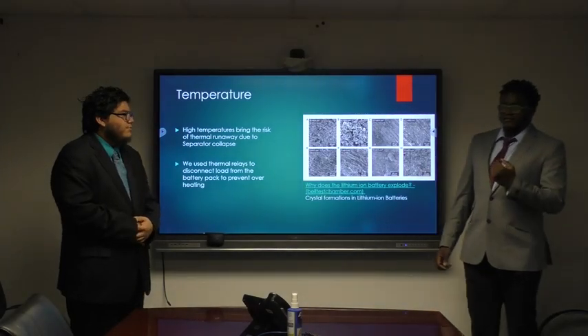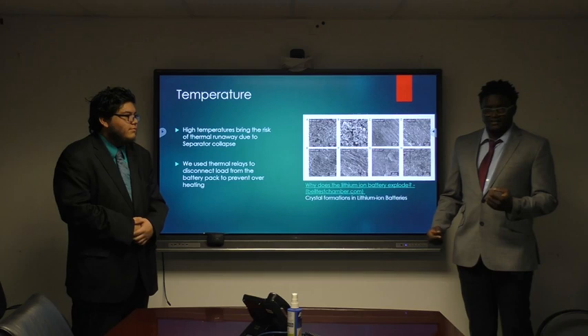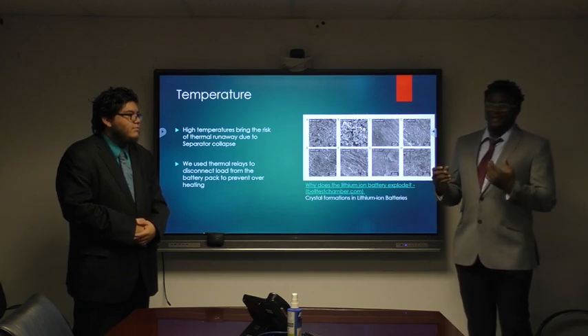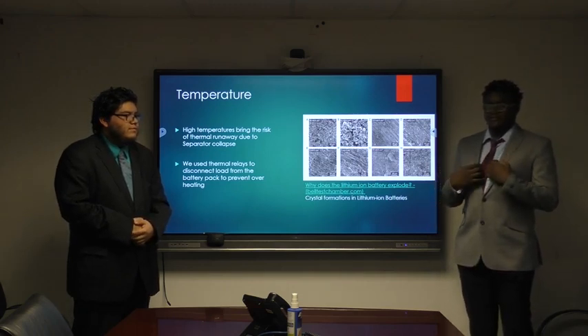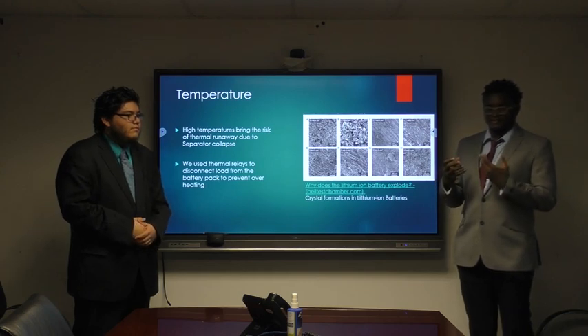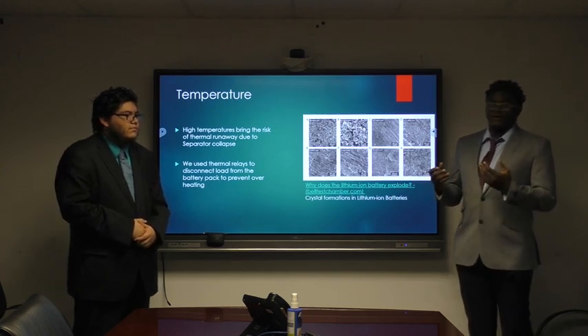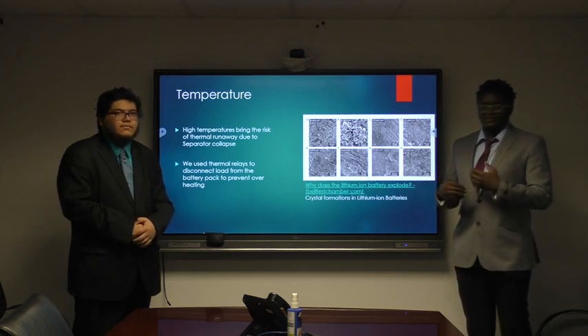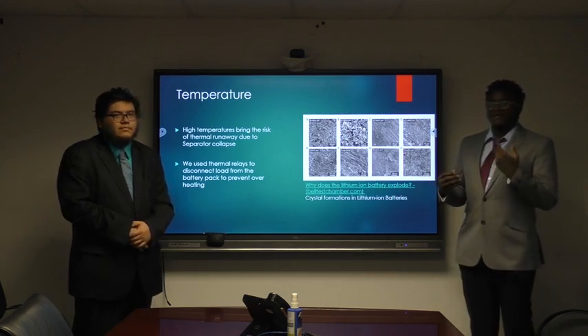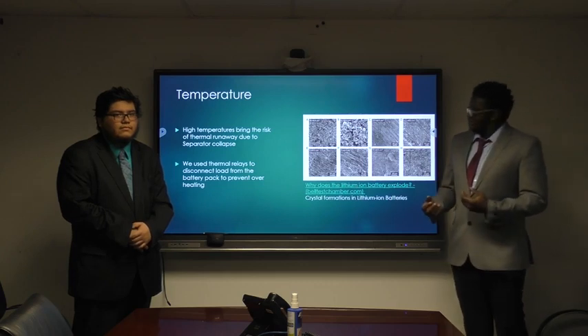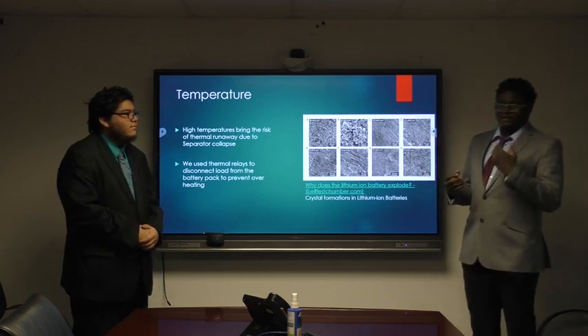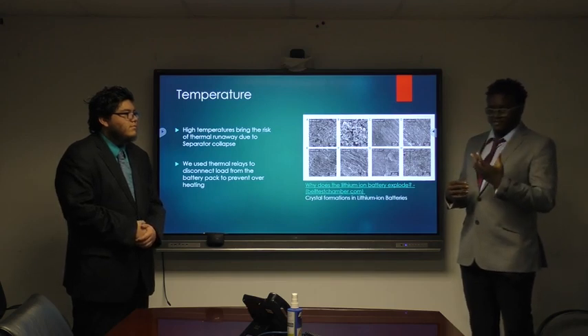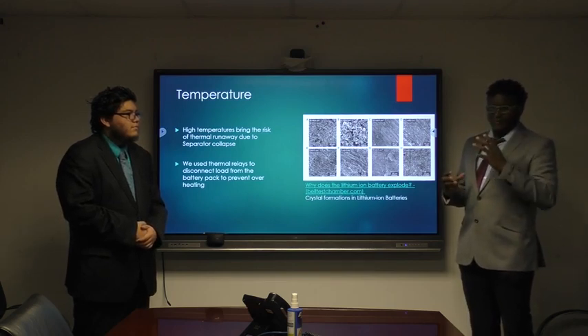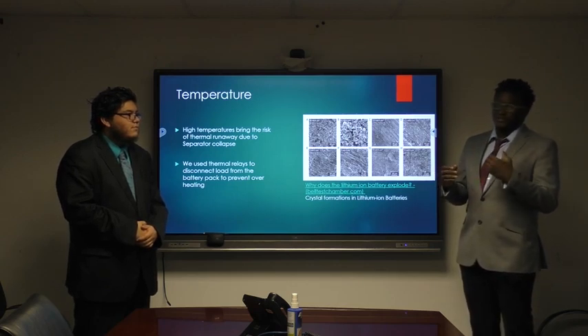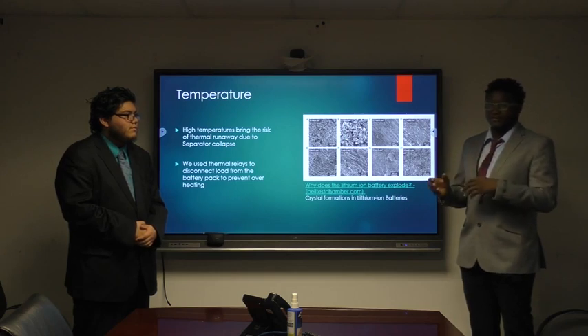Temperature management is important because once cells hit a certain point, the organic solvent that the lithium is dissolved in will break down and start an unstoppable reaction that will destroy the cell and may cause a cell explosion or fire. So we use temperature sensors in our BMS to keep the cell within a safe range of temperatures, to prevent the thermal runaway risk from occurring.